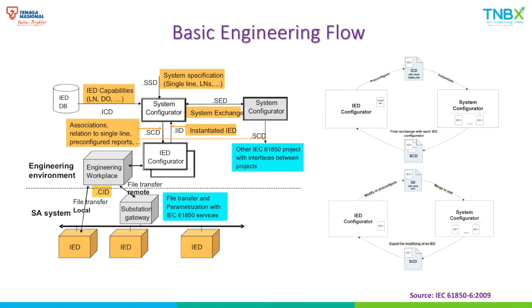In edition 2, we were introduced to the IID file, which can be used to modify configurations from earlier developed SCD files, or to pre-configure IEDs to instantiate certain elements. From experience, the latter is more prominent, where IID files are mostly used to instantiate elements as part of pre-configuration before importing the file into the System Configurator tool, or SCT tool.